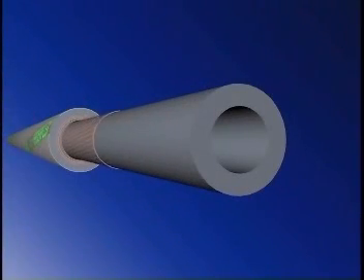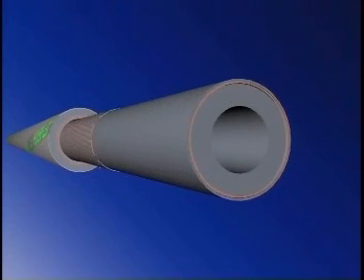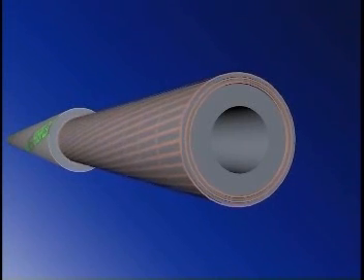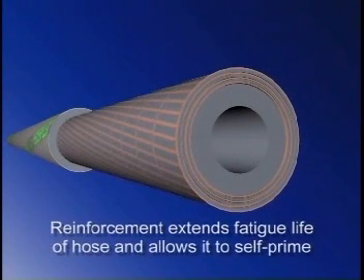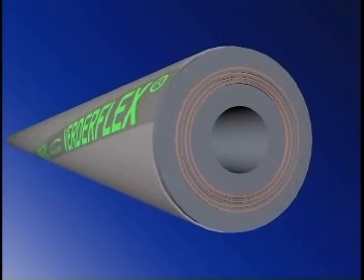After the liner comes the layers of fiber reinforcement. A Verderflex hose will always have at least two layers of fiber reinforcement. This reinforcement not only extends the fatigue life of the hose, but also allows it to self-prime. Lastly comes the outer cover, designed to withstand the abrasive wear of the pump rotor or rotor shoes.